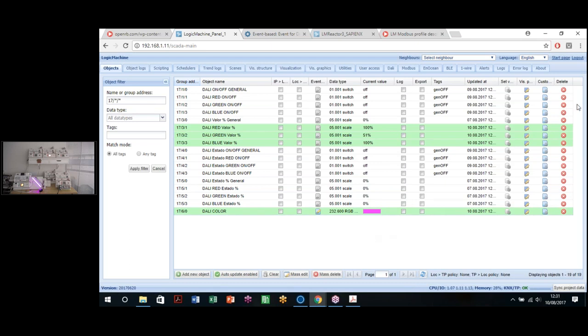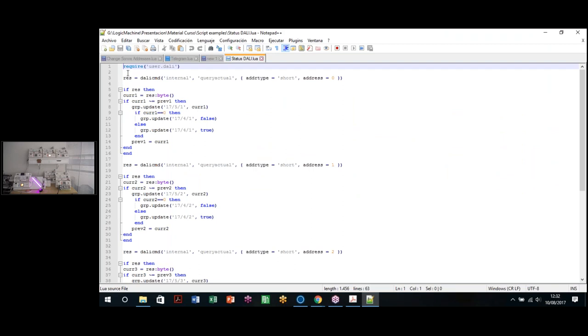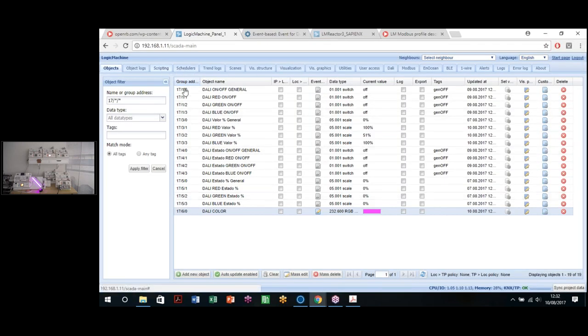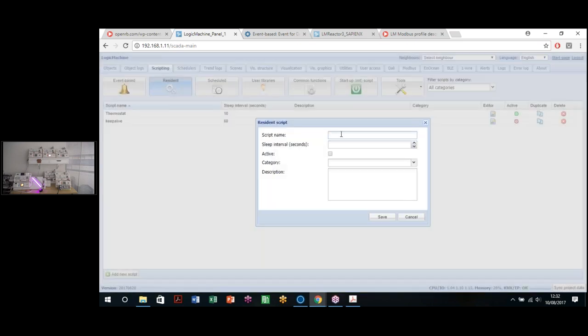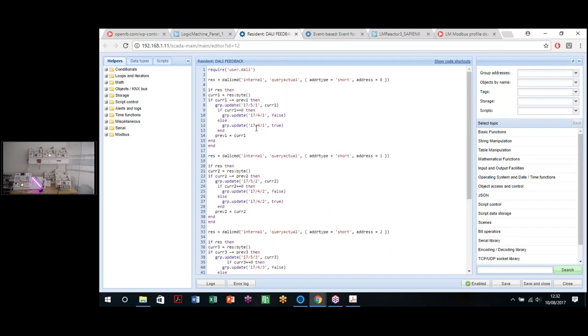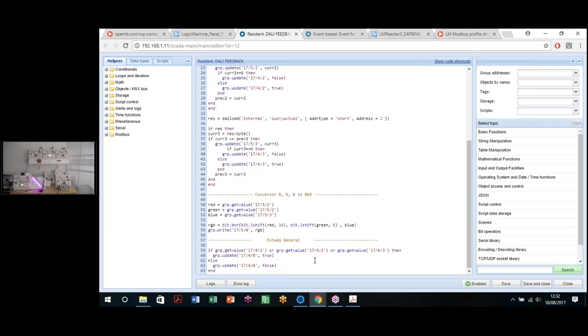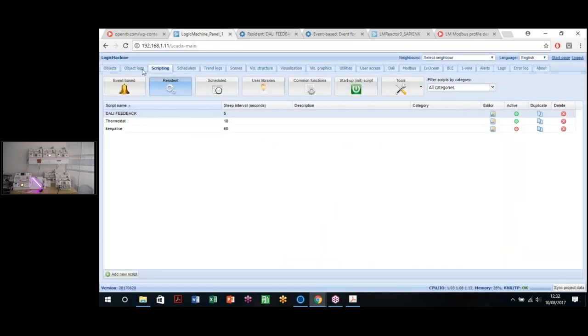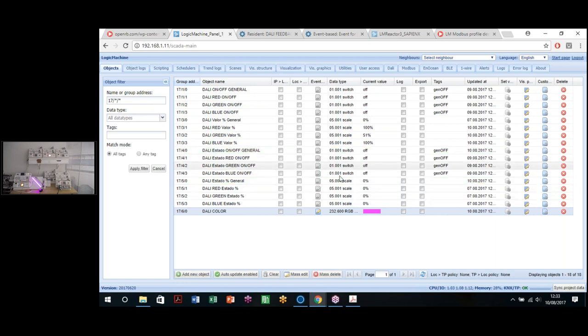We can also receive the information from the DALI. From the DALI channels, we can receive the information so we can have feedback on these objects. For that, we have a DALI status script that we are going to create as a resident script, so it will be repeated every few seconds. DALI feedback. Sleep interval, let's set it to 5 seconds, active. And the same thing. We open the editor, paste the code. This code may need some changes, but in this case I have it already set, so the only thing I need to do is click save.